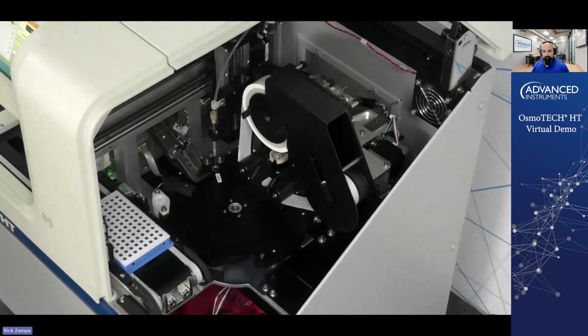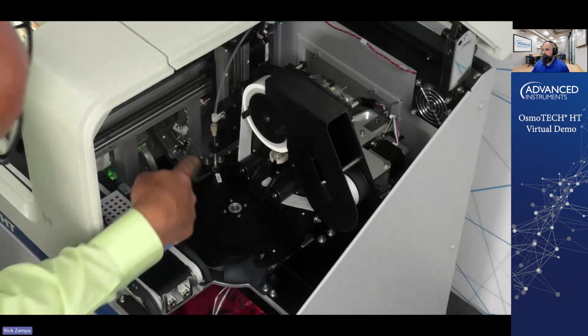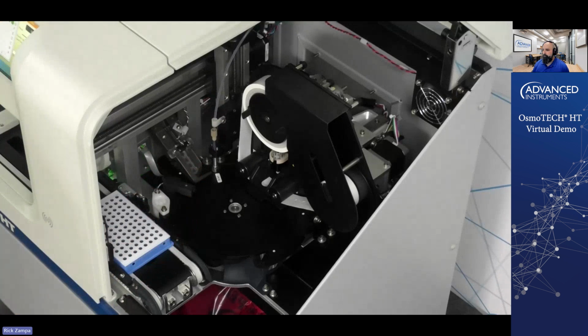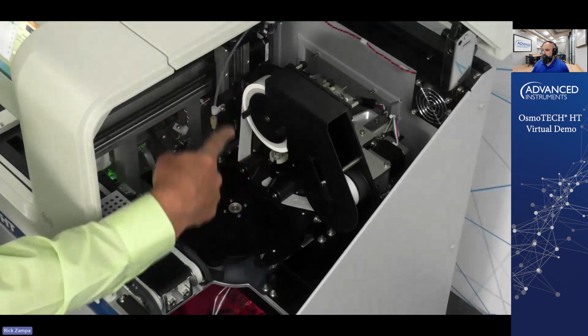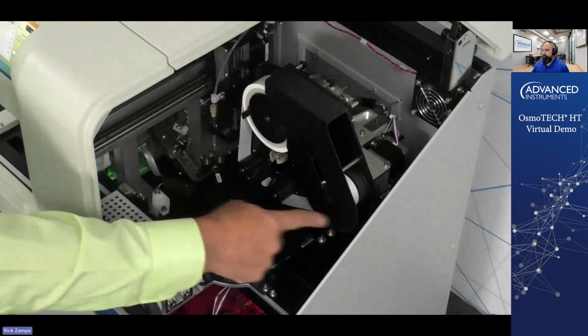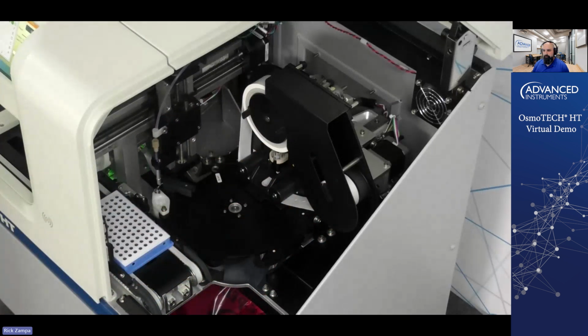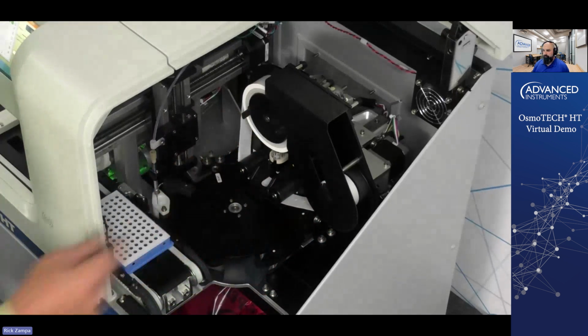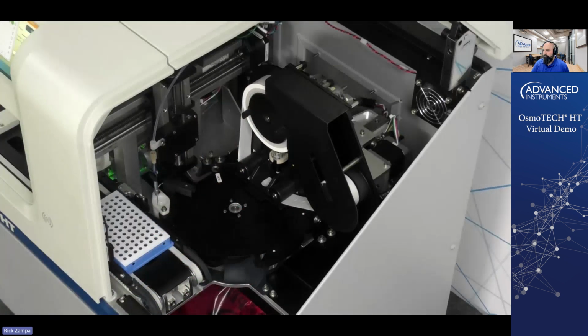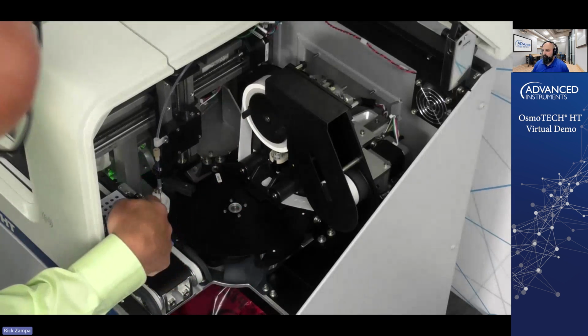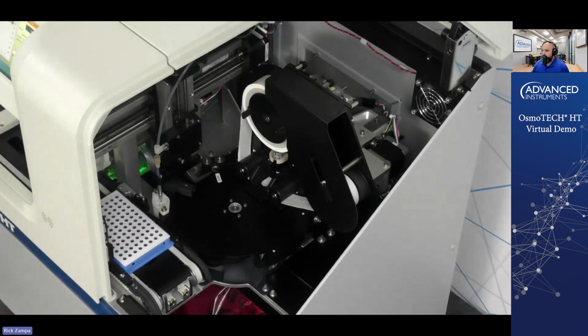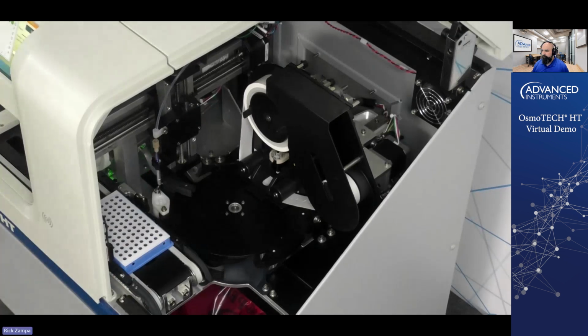Sample cup moves into position. The pipette's going to move in, going to move down. It's going to pipette the sample in there. As we're waiting, this is your cleaning reel that I mentioned earlier, where it punches through this after every test sample and cleans after every test sample. That's where it's going to clean between the samples. We've now pipetted the sample in. The system is now cleaning the pipette system over here in the cleaning well. It's pumping cleaning solution through the pipette well, and it's cleaning both the inside and the outside of the pipette at this point.